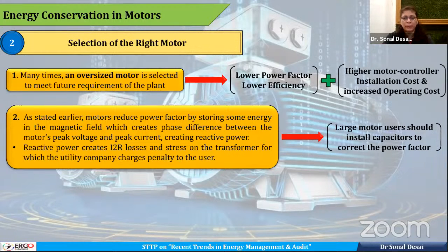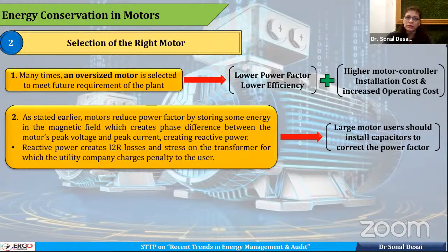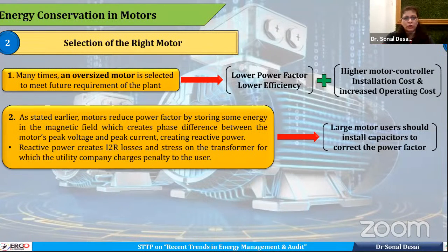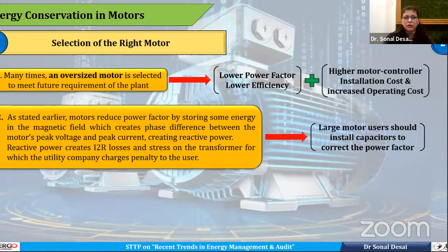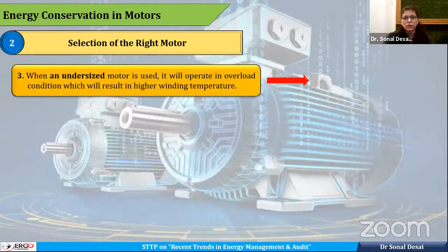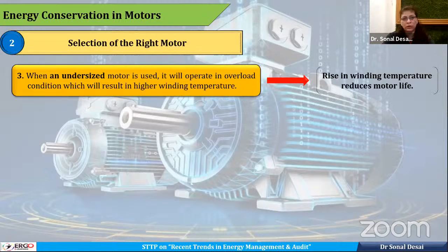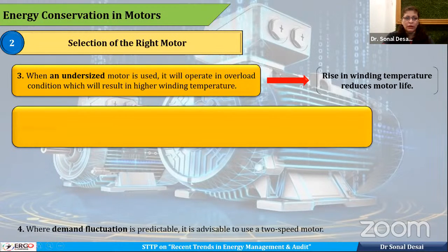That will have a dual benefit, that the penalty will not be laid to them, as well as the other equipment used in-house or used in the other nearby connection will also be safeguarded. So in selection of the right motor, first, when an undersized motor is used, it will operate in an overload condition. So it will have its effect on the life of the motor, its winding will be affected, and it will have a higher temperature operation.